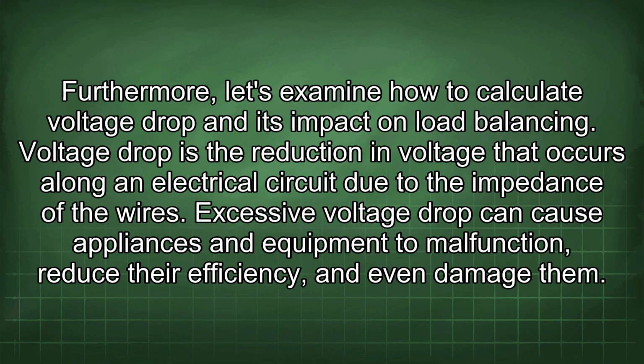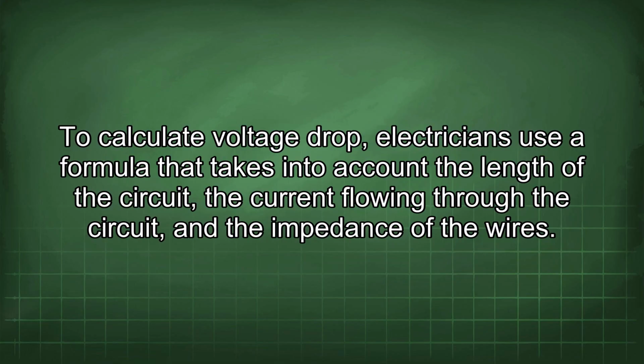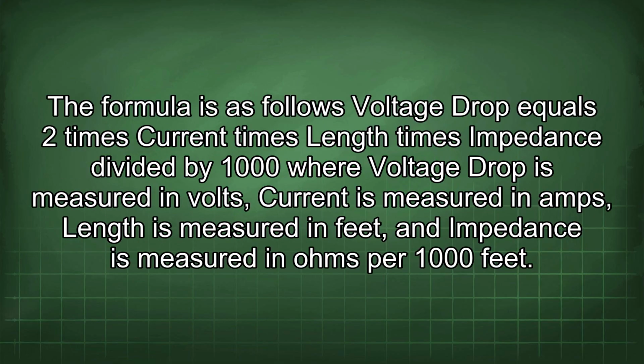Furthermore, let's examine how to calculate voltage drop and its impact on load balancing. Voltage drop is the reduction in voltage that occurs along an electrical circuit due to the impedance of the wires. Excessive voltage drop can cause appliances and equipment to malfunction, reduce their efficiency, and even damage them. To calculate voltage drop, electricians use a formula that takes into account the length of the circuit, the current flowing through the circuit, and the impedance of the wires. The formula is as follows: voltage drop equals 2 times current times length times impedance divided by 1000, where voltage drop is measured in volts, current is measured in amps, length is measured in feet, and impedance is measured in ohms per 1000 feet.